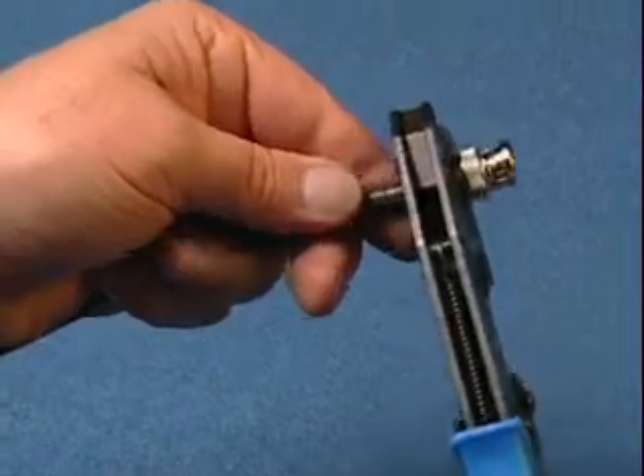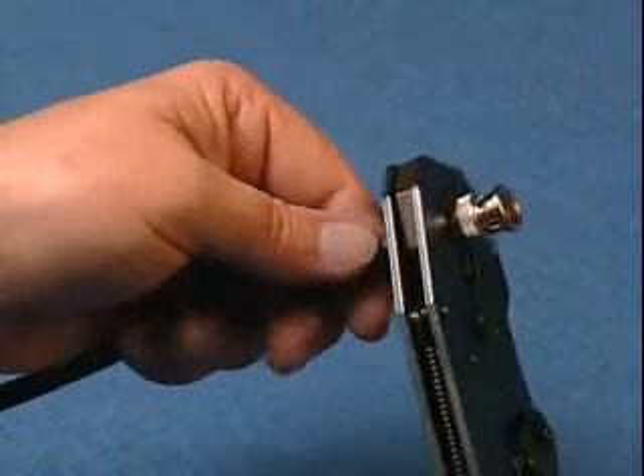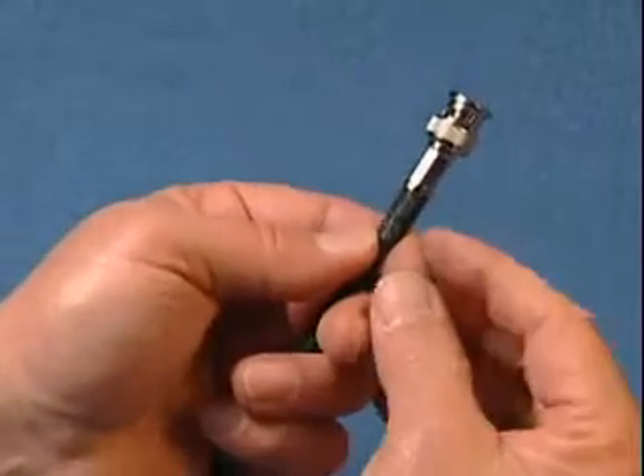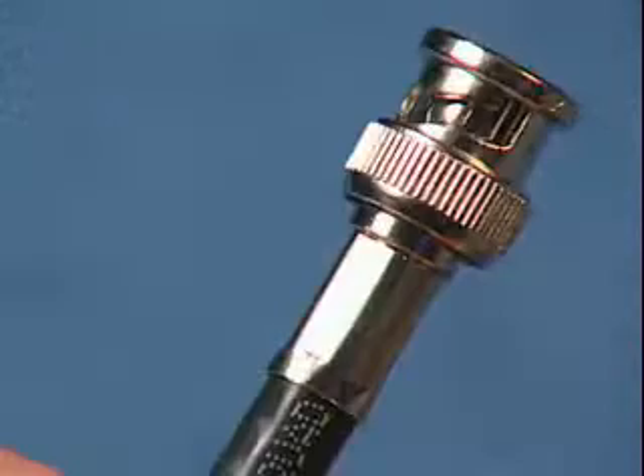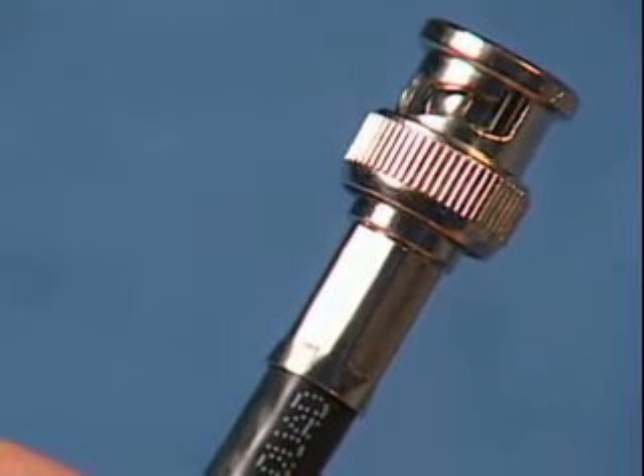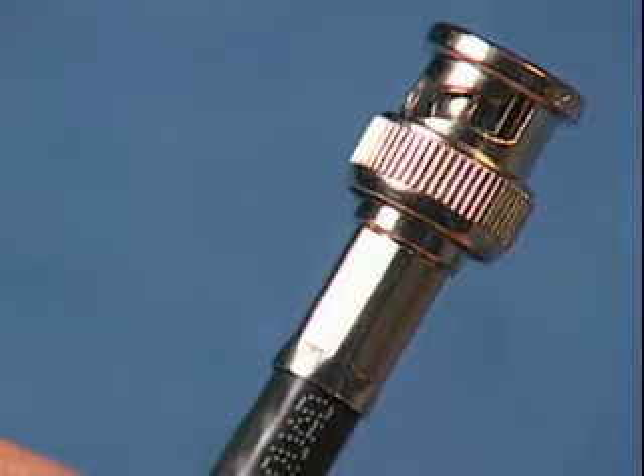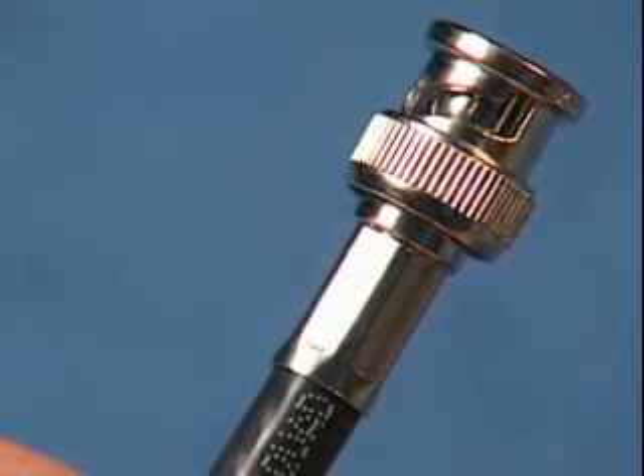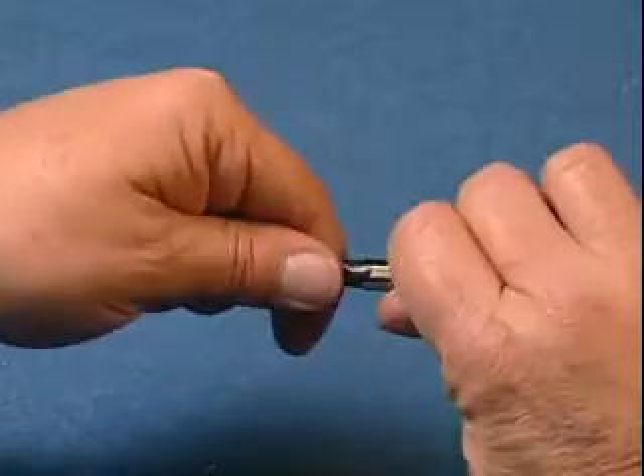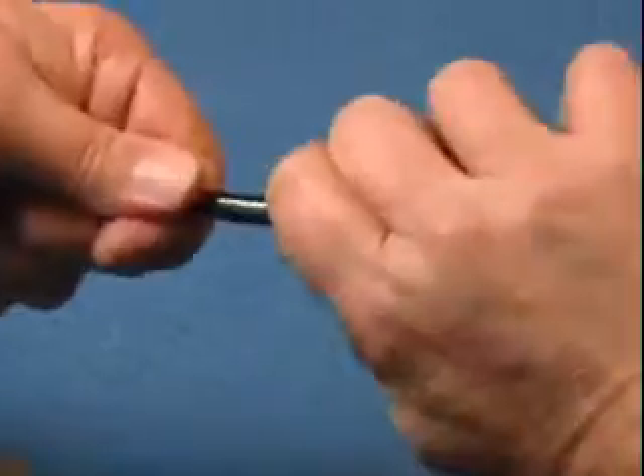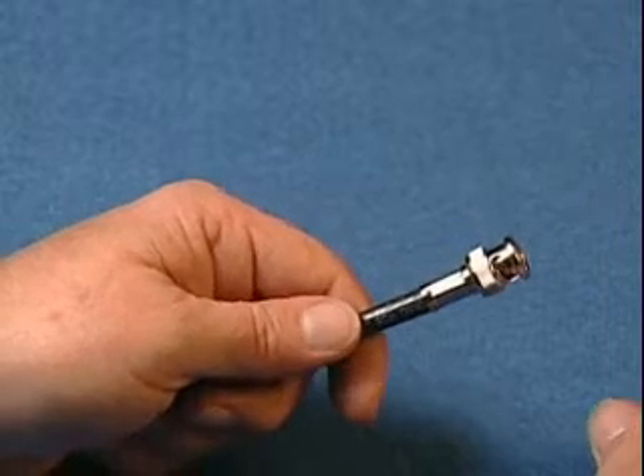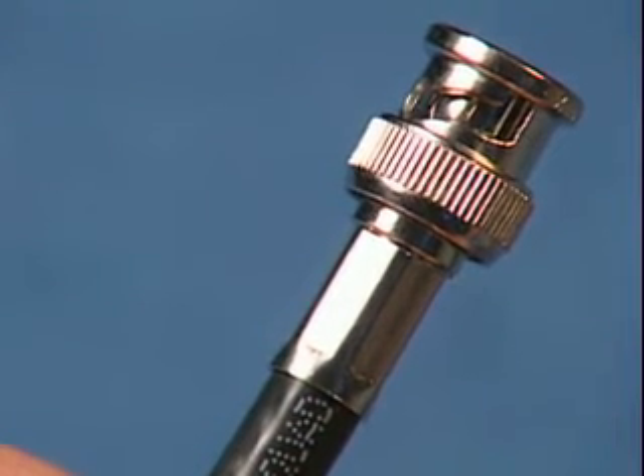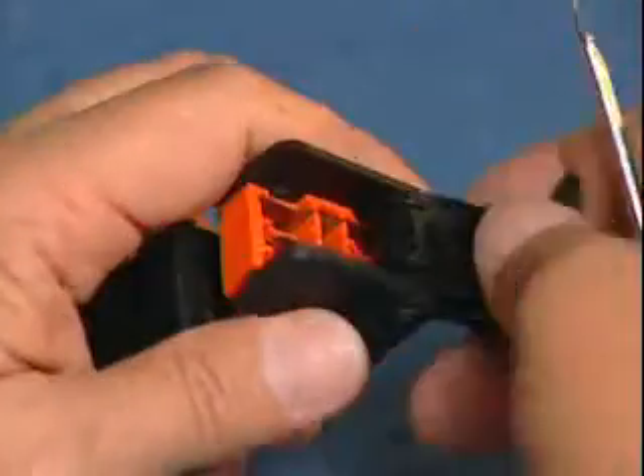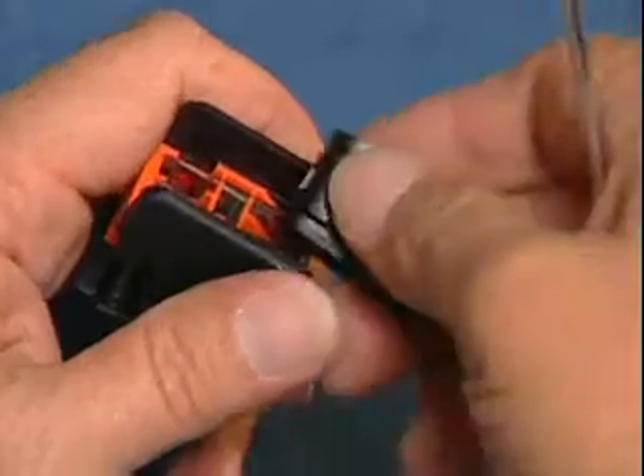Crimp the ferrule using the larger cavity of the crimp tool. Crimp the ferrule so that it is flush with the bottom of the connector body. You will notice that the ferrule is not crimped toward the cable and is crimped all the way to the bottom of the connector body. A properly crimped connector will not pull off the cable. This connection is now ready for testing. To convert the coaxial stripping tool for plenum cable, replace the memory cap marked PVC with the one labeled FEP.